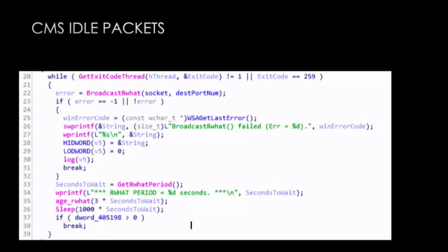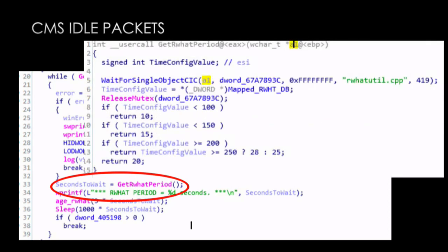Because the central monitoring station runs Windows XP and Windows 7, it was very simple to pull the binaries off and take a look at them to get a deeper understanding of these packets. With the help of IDA Pro, decompilers, and — we want to thank the vendor for leaving all the debugging symbols and names in the binaries, that was extremely helpful. This is the while loop that handles the packets seen on the network. At the top of the loop there's a function called 'broadcast R-WHAT' — that's the protocol being broadcast. Towards the bottom is the 'get R-WHAT period' function, which reads a value from a config file, multiplies it by 1000 in the Windows sleep function, confirming the ~10 second broadcast interval.